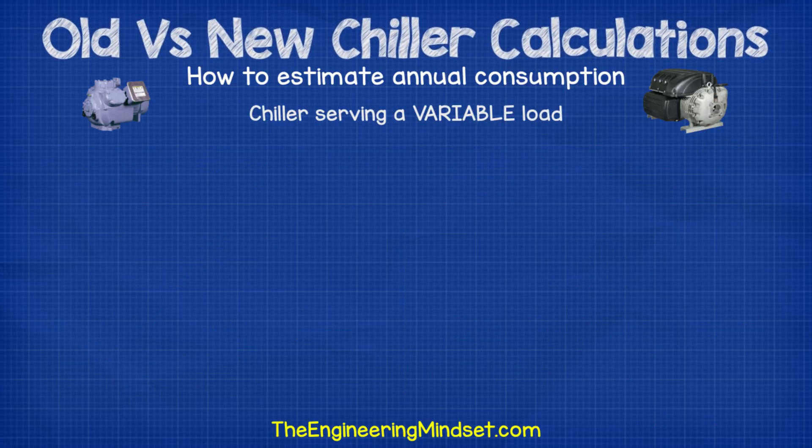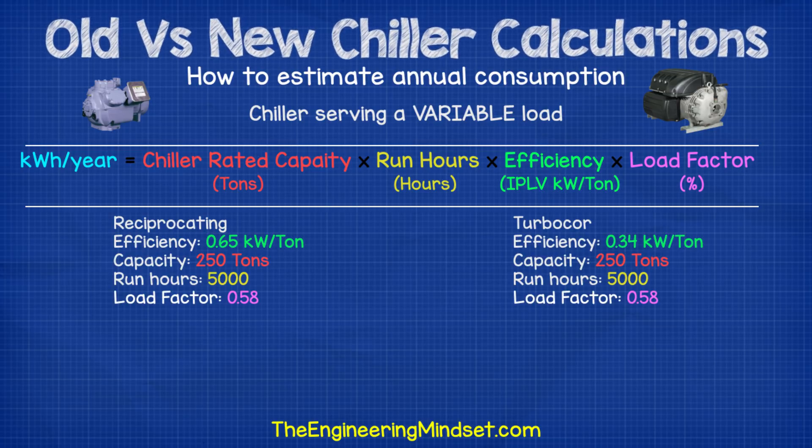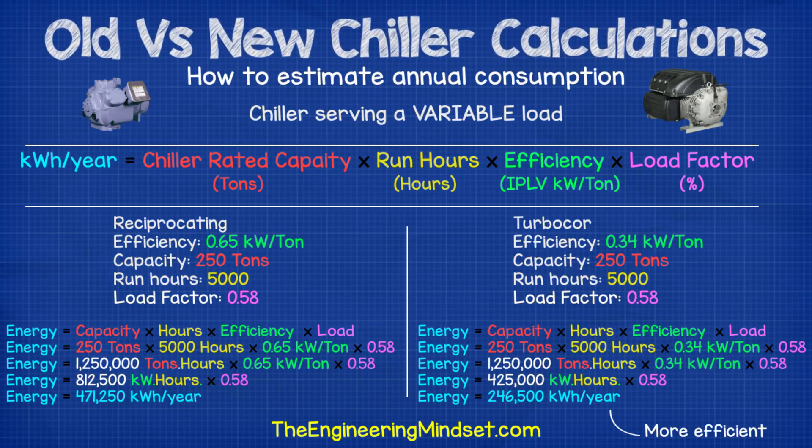If you have a chiller with a variable load, which is far more likely, you can use one of the following methods. If you have the IPLV kilowatts per tonne value, take the cooling capacity in tonnes, multiply by the annual operating hours, multiply by the IPLV kW/tonne efficiency, then multiply by the average loading factor — typically around 0.6 or 60%. For example, comparing a Turbocor chiller with an IPLV of 0.34 to a reciprocating chiller with an IPLV of 0.65, both rated at 250 tonnes with an average load factor of 0.58, operating 5,000 hours per year — the Turbocor comes out at 246,000 kilowatt hours per year whereas the reciprocating chiller comes out at around 471,000 kilowatt hours per year, resulting in a substantial saving of 224,000 kilowatt hours per year.